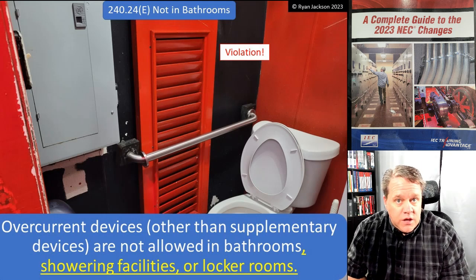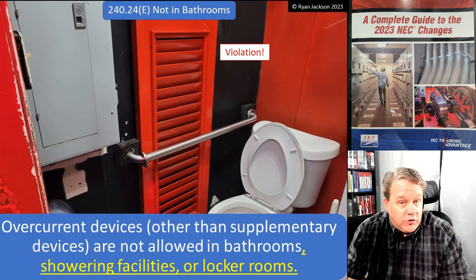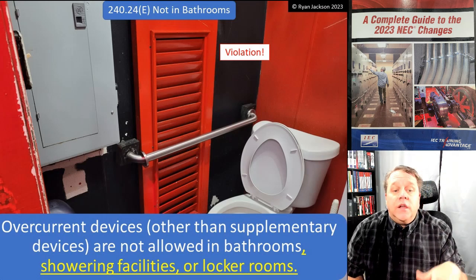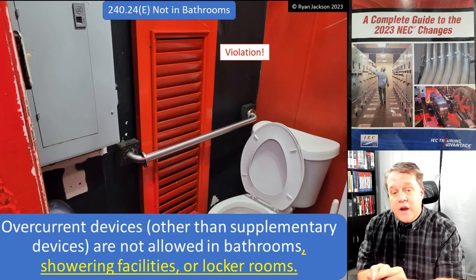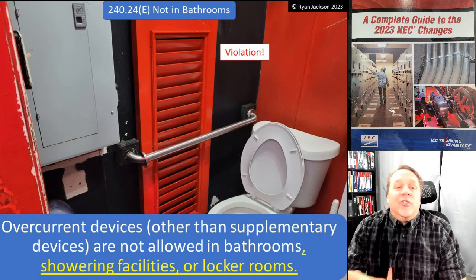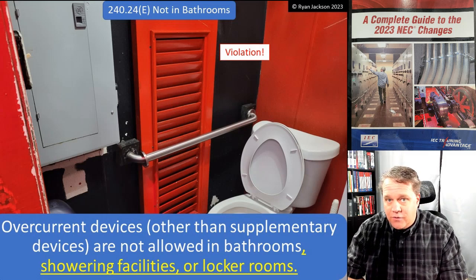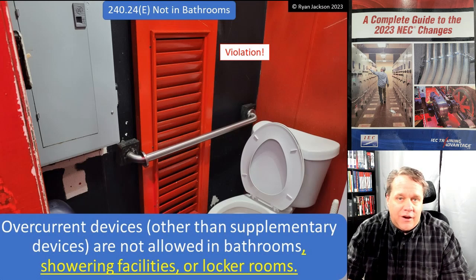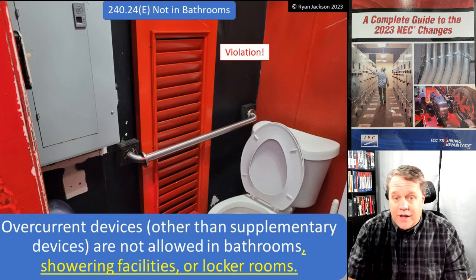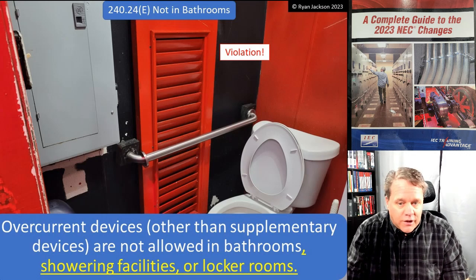240.24(E) — not located in bathrooms: overcurrent devices other than supplementary devices are not allowed in bathrooms, showering facilities, or locker rooms. It used to say only bathrooms of dwelling units and dormitories — now it says any bathroom. As a code instructor, I can't tell you how many times I was asked, "How come you can have a panel in a bathroom in commercial but not in residential?" I never had a good answer. The truth is, it probably never should have been allowed — either allow it in all or none.